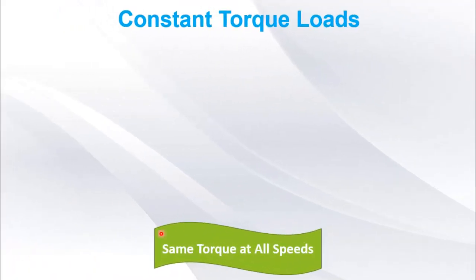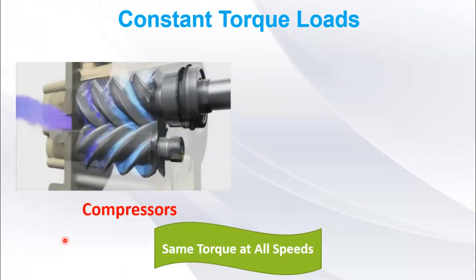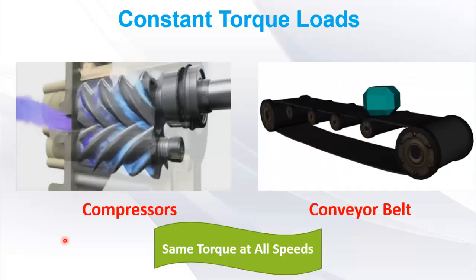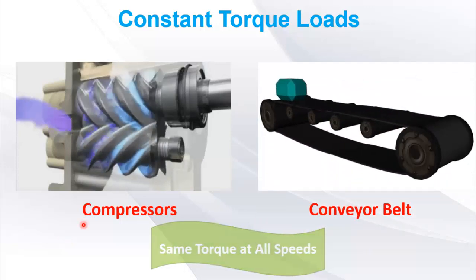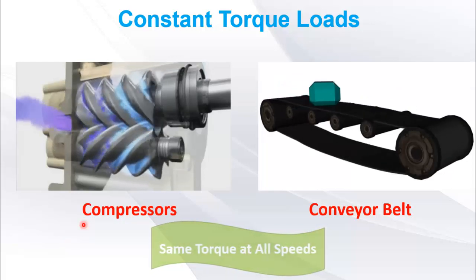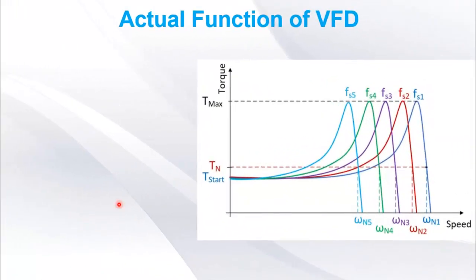Here, we have examples of constant torque loads. Compressors and conveyor belts are examples of constant torque loads. It means that the torque requirement of such type of loads is constant on all speeds. Let's see how induction motor can produce constant torque on different speeds. For this, we have to refer to torque speed characteristics of motor.